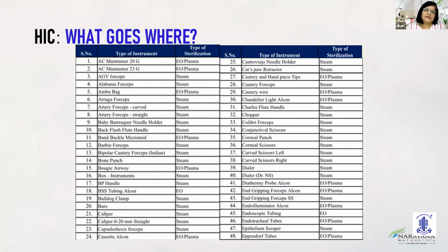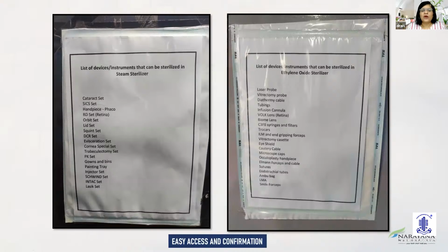Now, having said this, we know that we have a lot of instruments in our operation theater. Just have a look at this list. It basically helps me to understand what can be done where. For example, if I have a bone punch, I need to have a steam sterilization for it. If I have a caliper, it can go for steam sterilization. If I have something like a Colibri forceps, again it can go for steam sterilization. But at the end of the day, who's going to remember this? It is always better to put a list like this with your steam sterilizer and have a list of what all can be put over there. And if you have an ethylene oxide sterilizer, put a list over there of what can be utilized.